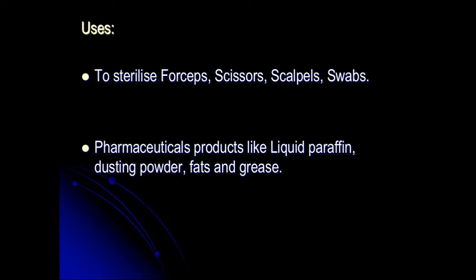While performing this process, the most important precaution you have to take is to wrap your material, that is the forceps, scissors, scalpel or the swab, in craft paper, and this material should be kept inside uniformly, so that there is a uniform flow of the hot air inside.